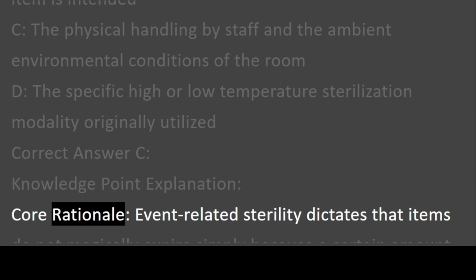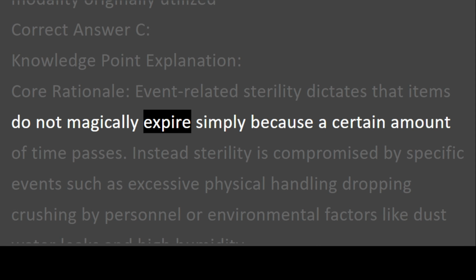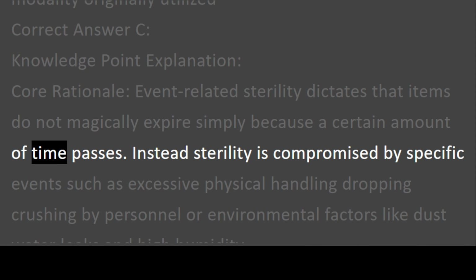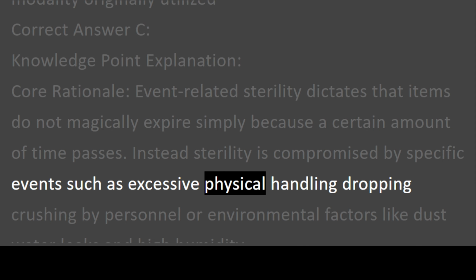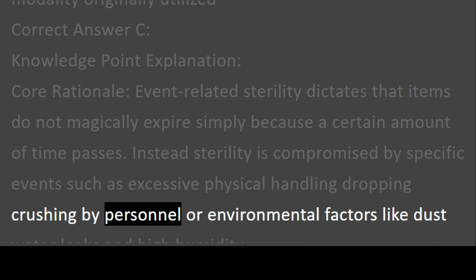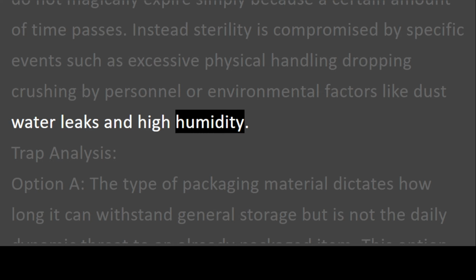Core rationale. Event-related sterility dictates that items do not magically expire simply because a certain amount of time passes. Instead, sterility is compromised by specific events such as excessive physical handling, dropping, crushing by personnel, or environmental factors like dust, water leaks, and high humidity.